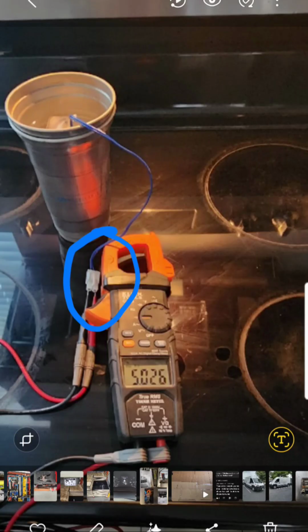And what I did was I put the probe into a cup of ice water, and you should get resistance on there. You want to check your resistance across that probe, and we do got resistance. And then when I removed the probe from that ice water, I could see that it was sensing the temperature change, and then the resistance would go down. So that's a quick test that you could do to test out the probe.